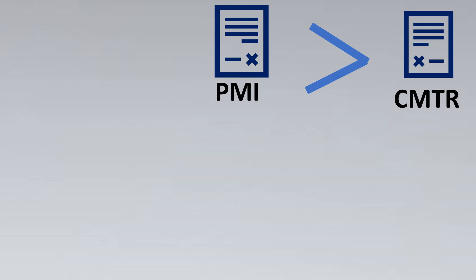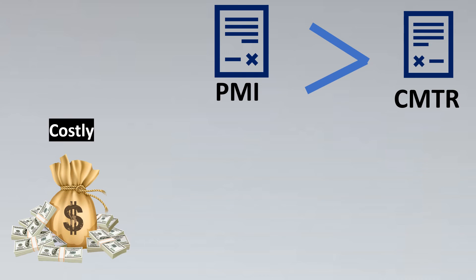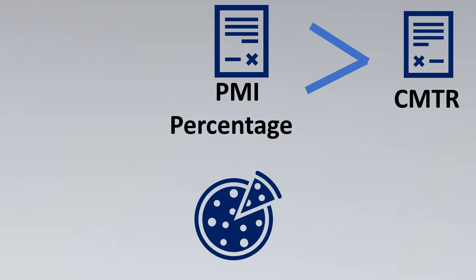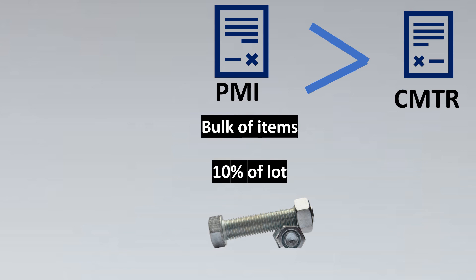Is PMI greater in scope than CMTR or the material certificate? With respect to cost, PMI is far more expensive than the material certificate. For that reason, sometimes a special consideration is made: only a percentage of a lot is checked via PMI, especially for bulk items. For example, for studs, bolts, and similar bulk items, you might check just 10% of the lot — only a random 10% sample is tested.